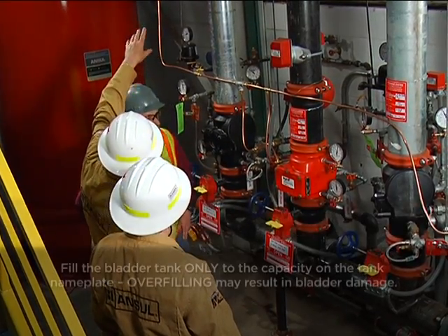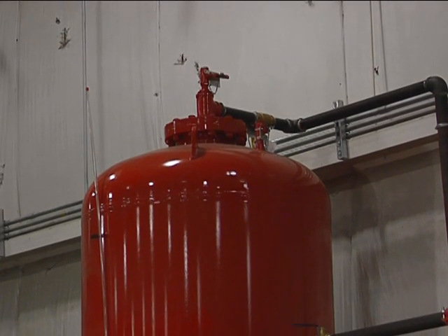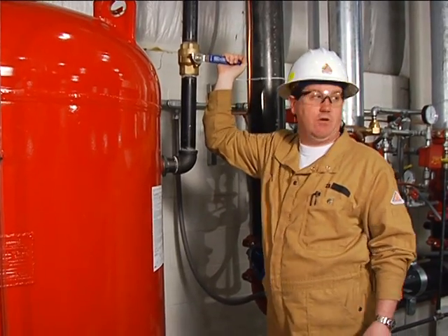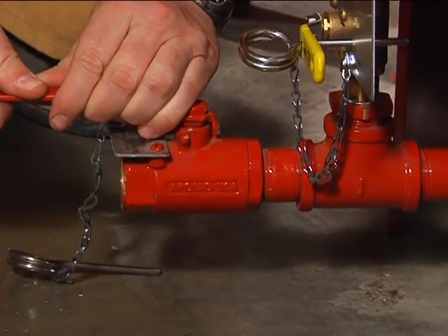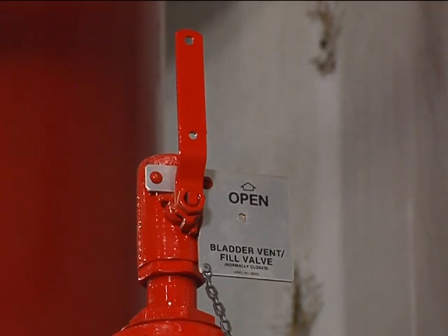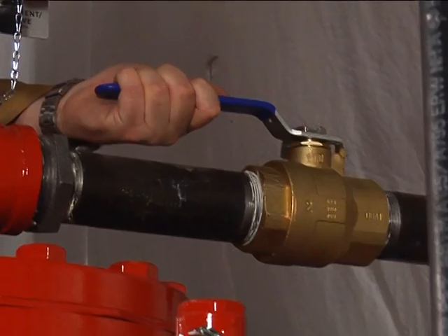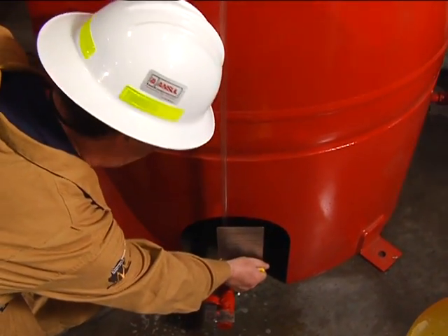On a new system, you'll need to prepare the bladder tank for its first fill. Remove the plastic shipping plugs from all bladder tank trim valves. Make sure the bladder tank valve handles are in the following positions: Water Inlet Valve – Closed; Tank Shell Drain Valve – Closed; Bladder Drain Fill Valve – Open; Tank Shell Vent Valve – Closed; Bladder Vent Fill Valve – Open; Concentrate Isolation Valve – Closed. If provided, make sure the sight gauge valve is operating. Next, connect the vacuum hose to the tank shell vent valve using pipe fittings and duct tape.